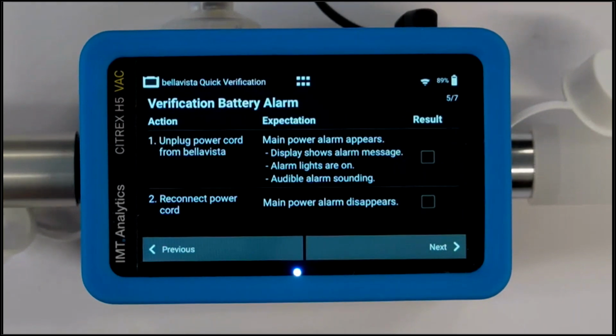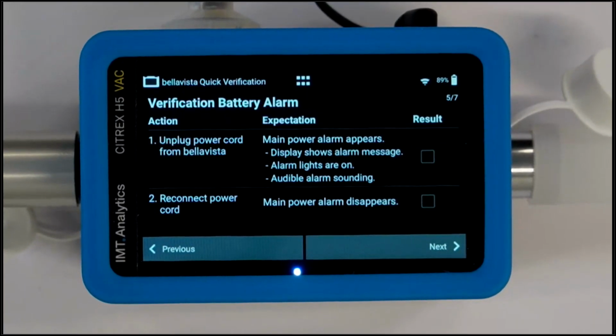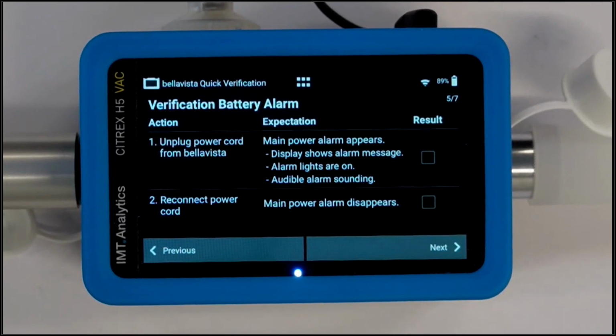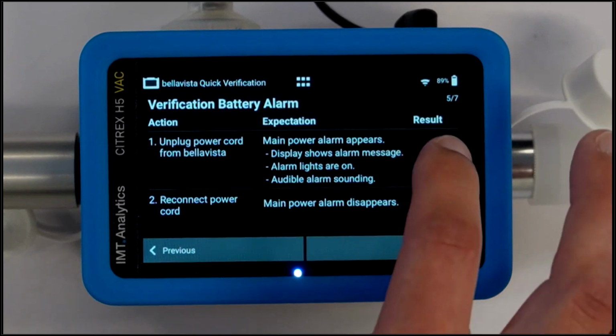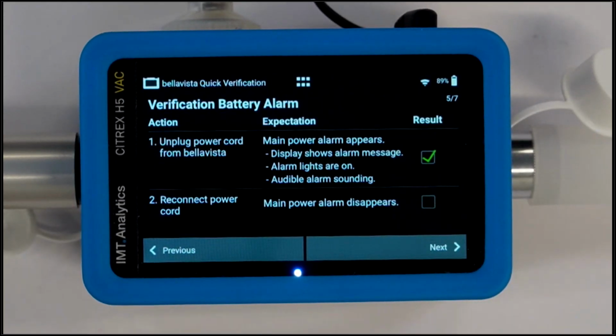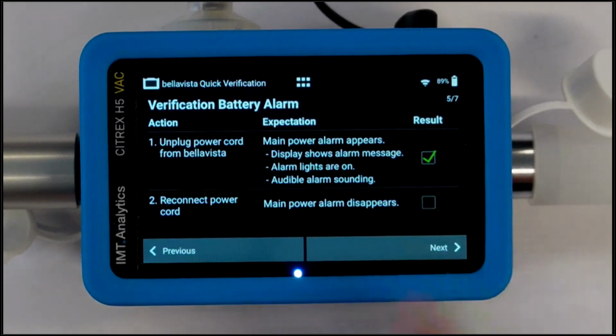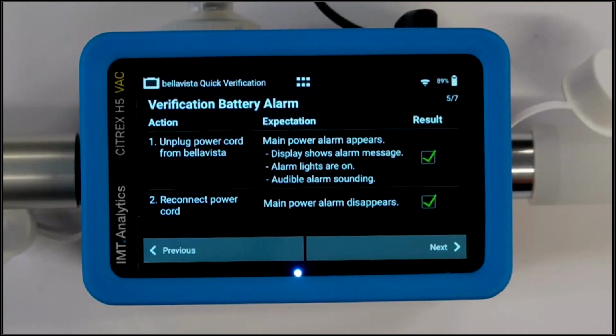On the next page, we have to test if the ventilator can run from battery. So I have to disconnect my mains power cord. And then again, I have to confirm that the alarm is being triggered and that the machine runs from battery. And when I connect power back up, then it should recognize that as well. That happened too. So I confirm this here in the app as well.